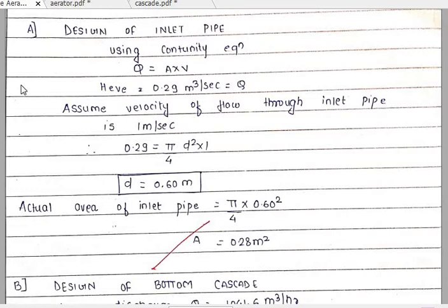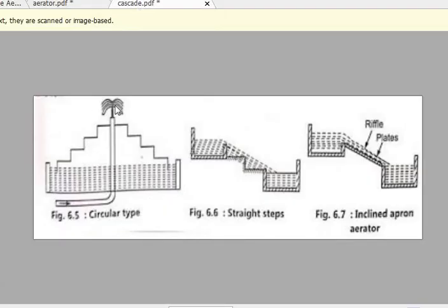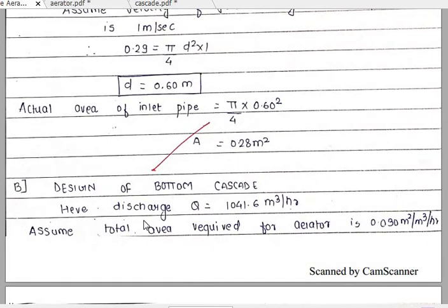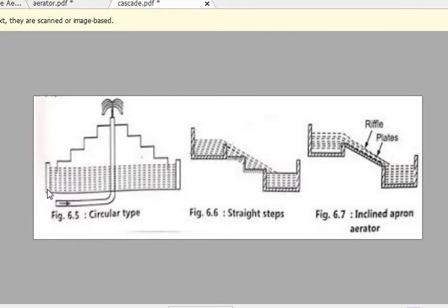To summarize the inlet pipe design: we have simplified the inlet pipe by substituting the velocity of water through the pipe as 1 meter per second and we get the diameter of the inlet pipe as 0.6 meter, and the total area of the inlet pipe as 0.28 meter square. Now moving to the second part — the design of the bottom cascade.